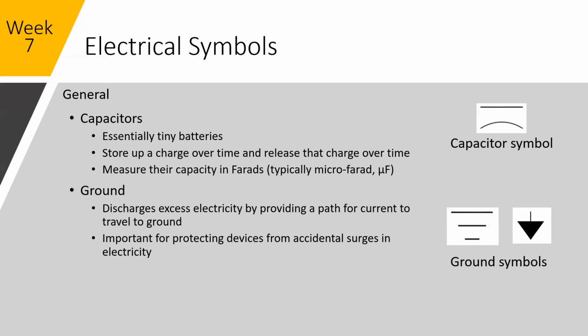And then grounding. So these are the two symbols you'll see for grounding most of the time. Sometimes they're interchangeable. Other times, depending on your project, they may not be. Grounding is important for electrical circuits to prevent surges. You need a place for shorts, surges to go to ground. But when you get into some complicated control equipment, analog signals, sometimes you need to have separate grounds. So you do have to pay attention to building ground versus earth ground versus isolated grounds.